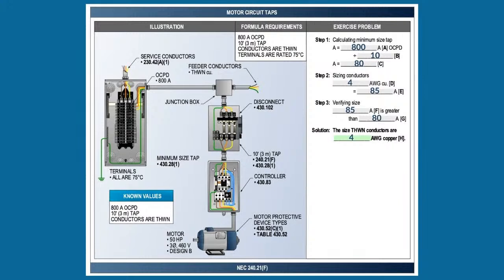Yeah, let me go on that. You said inverse time. So we'll say we do an inverse time circuit breaker. If I look at that motor, that's a 50 horsepower, 460 volt, 3-phase design B motor, and I'm going to size my inverse time circuit breaker. If I go and look at 430.6(A)(1), it tells me that whenever I'm sizing the conductors or overcurrent device, to use the tables in 430.247 through 250. Well, since this is a 3-phase, I'm going to use table 430.250, and that 50 horsepower at 460 volts is going to give me 65 amps.